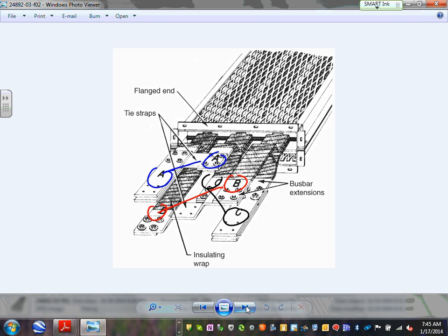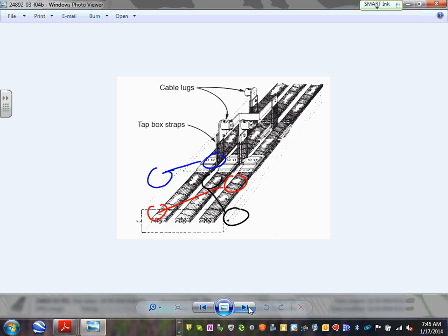To maintain the integrity of the impedance of the busway, every certain distance they transpose them. The bus that was at the bottom, they put at the top, and the one at the top, they put at the bottom. Any comments, any questions about the structure of busway? You guys have seen it yesterday, and you looked at it.